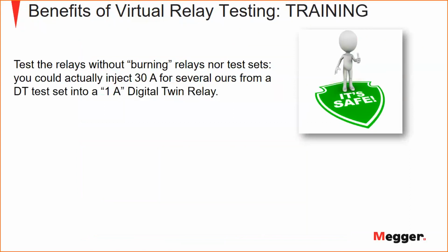You can test the relay without burning it. I mean, for example, for training, you can inject 30 ampere. We can inject 60 ampere, but not continuously. You can inject 30 ampere continuously for several hours from a digital twin test set into the 1 ampere digital twin relay without it burning.